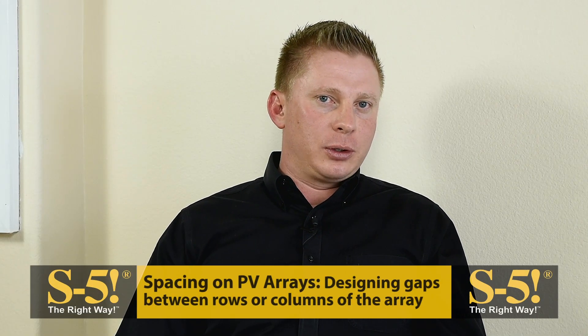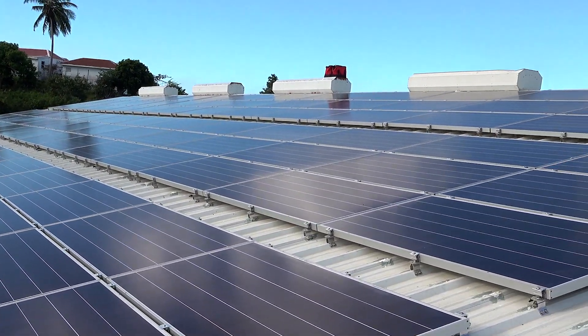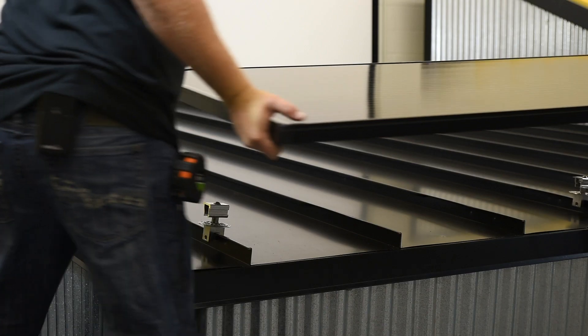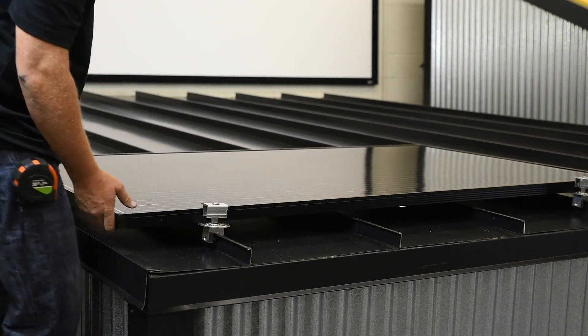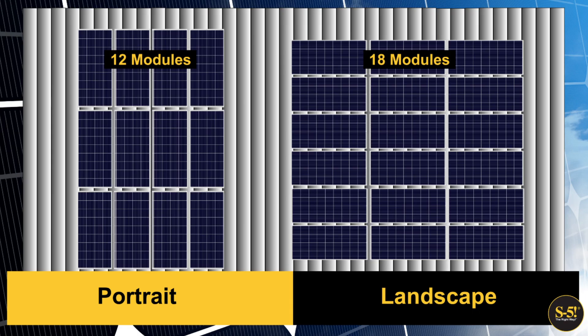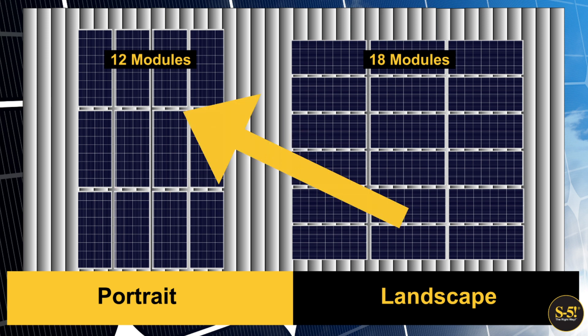All right, Nick, let's go ahead and begin. What is meant by spacing of PV arrays? Spacing of PV arrays involves designing gaps between rows or columns of the array. These gaps can be used for walk spaces, to design visual symmetry or patterns into the array, and to allow the module manufacturer's mounting zones to lie directly over the seams or ribs of the roof. With a direct-attached method, you're often going to be mounting the modules in the landscape orientation, which refers to when a module is mounted horizontally as opposed to vertically with the portrait orientation. We're also going to talk about placement of the array on the metal roof relative to the edges of the roof.